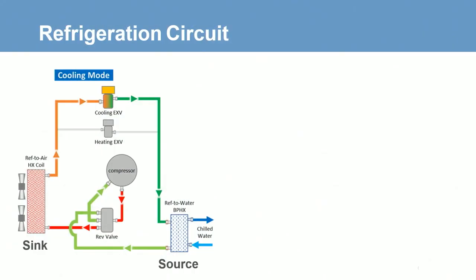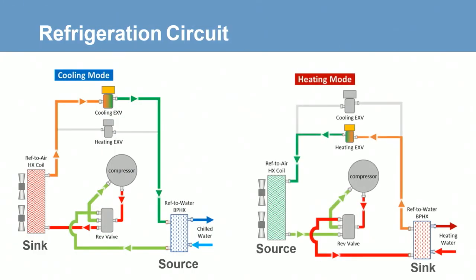To change over to heating, the unit reverses the refrigerant flow through the coils and changes to the heating expansion valve. In heating mode, the refrigerant to air coil is the energy source in the circuit, absorbing heat from the outdoor air, while the refrigerant to water coil is the energy sink by rejecting heat to the hot water circuit. When the unit needs to go into defrost mode, it essentially goes into cooling mode to send hot refrigerant to the outdoor coil to melt the frost.